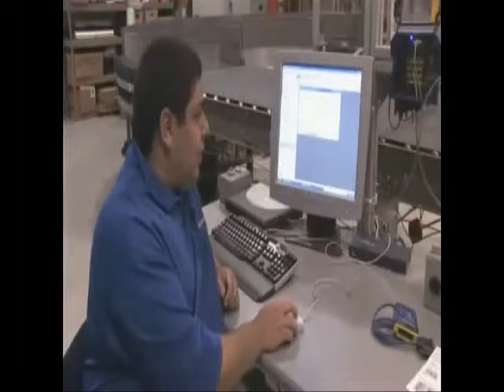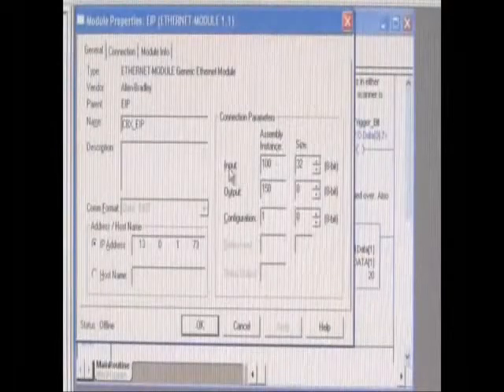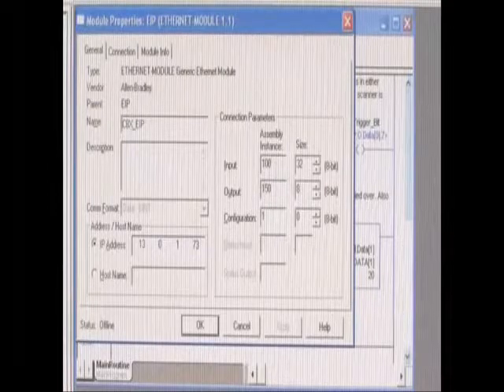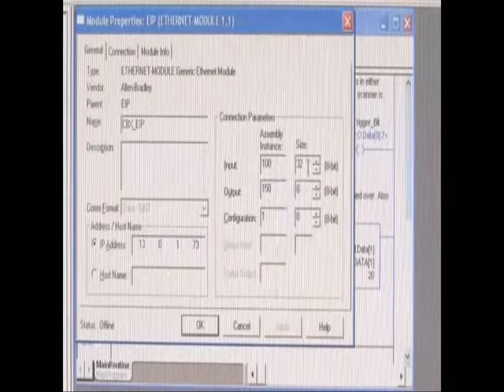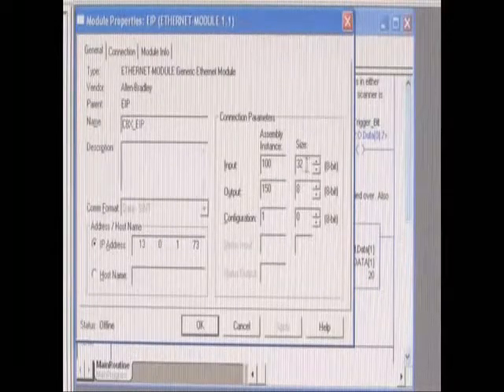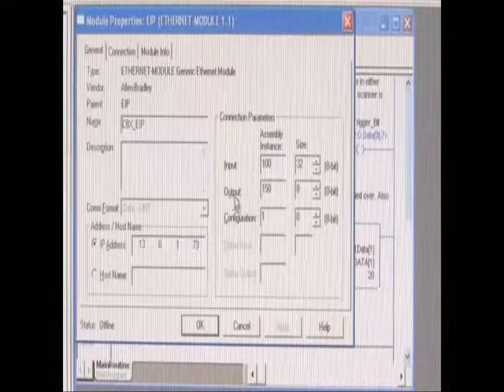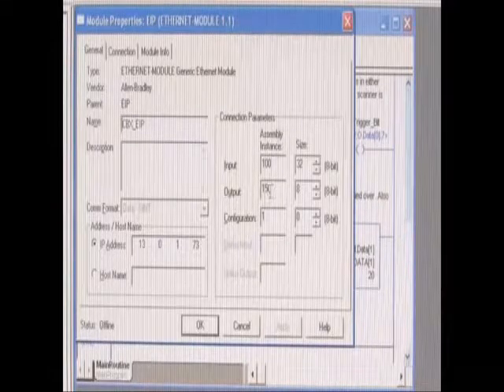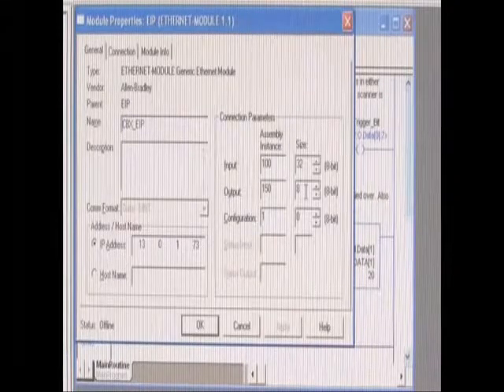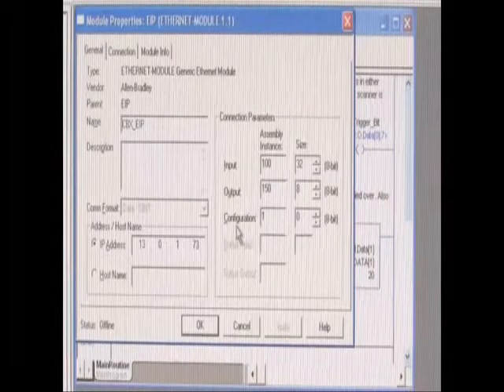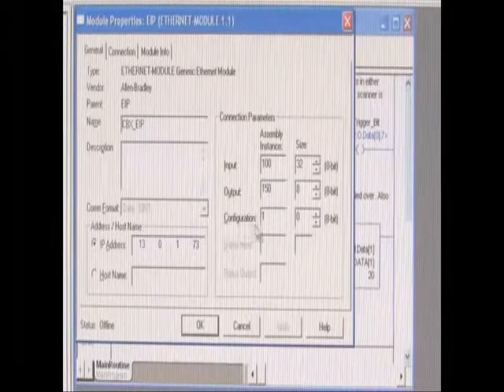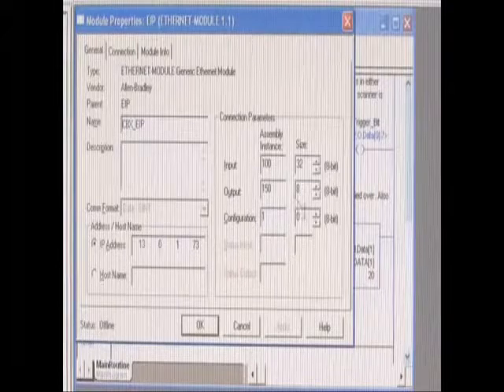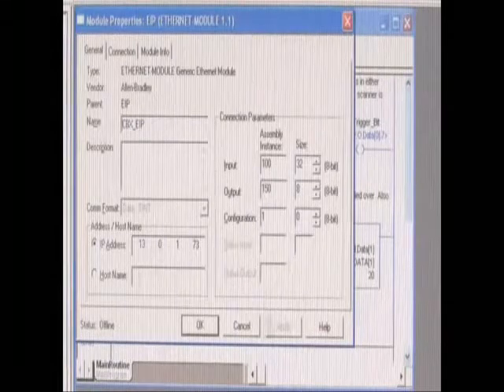We need to use, the assembly instances are for input 100. In this example, I'm using a size 32. Output, the assembly instance is 150 and using a size 8 in this example. Configuration assembly instance is 1 and the size is always 0.